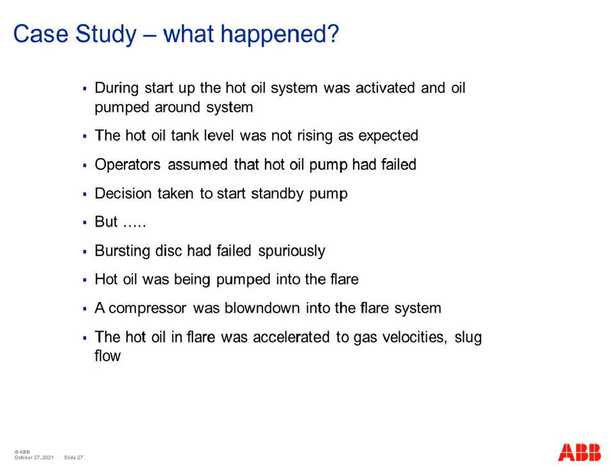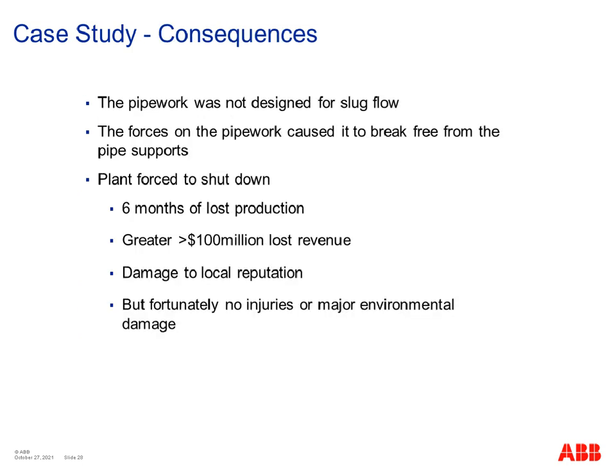It so happened that a compressor was also being blown down into the flare system at that time. So the hot oil in the flare system was then being accelerated by this gas from the compressor, and you ended up with slug flow in the flare system of this liquid and vapor together. The pipework wasn't designed for slug flow. It caused a lot of stress in the system. So the forces on the pipework caused it to break free from the pipe supports. This forced the plant to shut down because the flare system had broken free. It was badly damaged. This caused 6 months of lost production, greater than $100 million of lost revenue, and a lot of damage to the local reputation of the company involved. But luckily, in this case, there were no injuries and there was no major environmental damage that took place.